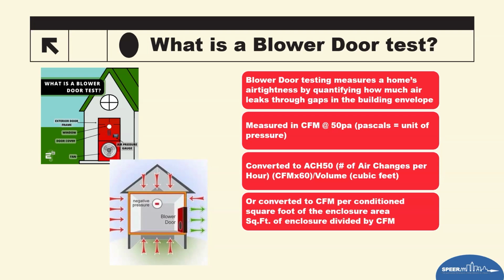It measures the air moving through the fan in CFM, that's cubic feet per minute, at a pressure differential of 50 pascals. That's a pressure difference from inside to outside. So the pressure could be anything, but the difference has to be 50. That's the limit that's required by the standard and is written into the IECC. So during this time, the house is experiencing a pressure differential from inside to outside of 50 pascals.